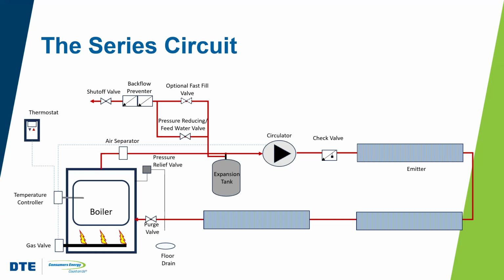They're great for really small homes. And again, there's a single flow rate, right? There's a single flow rate through all the piping and through all the emitters. The pressure drop for this system is the sum of the pressure drops across each of those individual pipes. Some of the downsides of this system are that, the big thing, is that water temperature decreases as it flows through each emitter. So emitter 3 doesn't see the same water temperature as emitter 1.